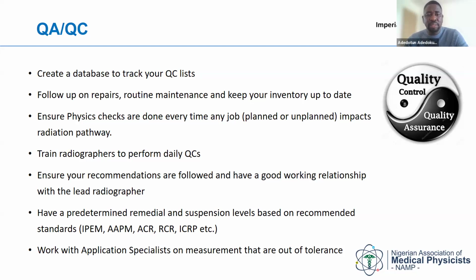Have a predetermined remedial and suspension level. As a good DR physicist, at the point when you do your acceptance and commissioning, it is important that you have what you call remedial levels, where some measurements are out of specification, and you can still, while you ask the engineer to come and work on them, use the equipment for clinical work. But when it goes beyond a certain level, it could be 10% from baseline, it could be 20% from baseline, then you have a suspension level. All of this makes you a physicist.